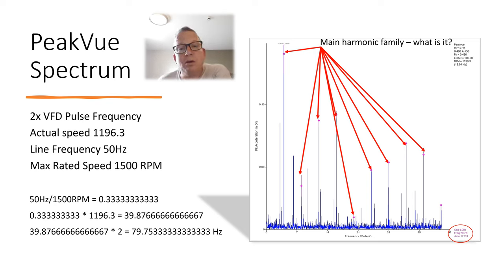So what we've got to keep an eye out for is the electrical firing frequency, two times the pulse drive frequency, which can be noisy on some motors, especially if it's not got the best cables installed. So 50 divided by 1500 gives us 0.333 recurrent, times that by the actual speed and times by two because we've got north and south.